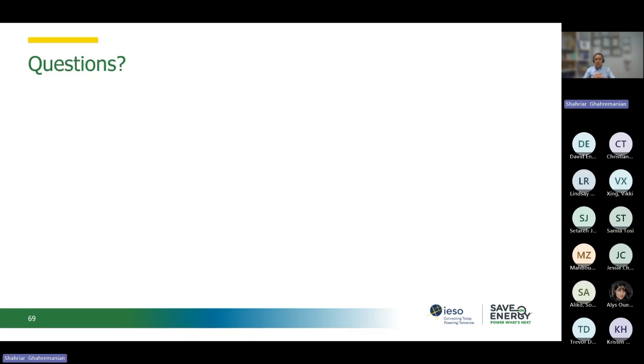The only reason I can point to is affordability. Technologically, heat pumps are more efficient. If you look at the basic engineering thermodynamic cycle, heat pumps are more efficient than combustion fuels—the best boilers we have are 84% or 90% efficient, but a heat pump can deliver heat at more than 100% efficiency. So the only reason I see in projects is affordability or the initial cost. At the same time, design needs to be done by professionals, since it depends on the facility, the climate location, and the energy hierarchy I showed you—it's better to go through all of them and reduce the load within the facility. But I haven't seen any applications where a heat pump cannot be installed.